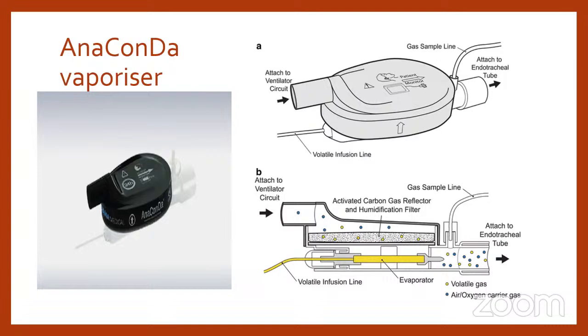So when your bellows is not working properly, yes, sir. And whenever the bag or bellows are not working properly, this is one area where we expect the leakage from. One more thing is, when the patient is not recovering, at times we may forget to close the vaporizer. Yes, sir. Okay. And next thing is, even though we are putting a high concentration on the vaporizer, pressures are not reducing.